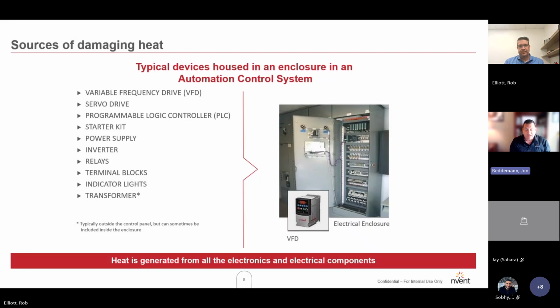And as we populate these enclosures, especially now, we're seeing much higher densities and much smaller enclosures, which is leading to much higher heat loads. Once we close that door, we are capturing all of that heat inside of that enclosure, which is driving the internal temperatures much, much above what ideally we'd like to see, right? Yeah. Well, depending on the generation of the VFD or the soft start or whatever, there's also spacing that you have to have between the units, just for that airflow and cooling. And a lot of times, like you said, people in control shops just want to put as much density as they can because they want to make the overall size of the enclosure smaller.